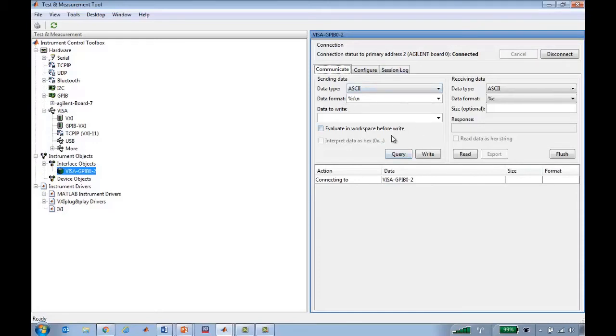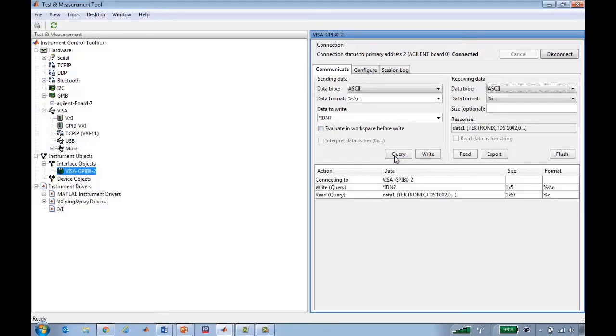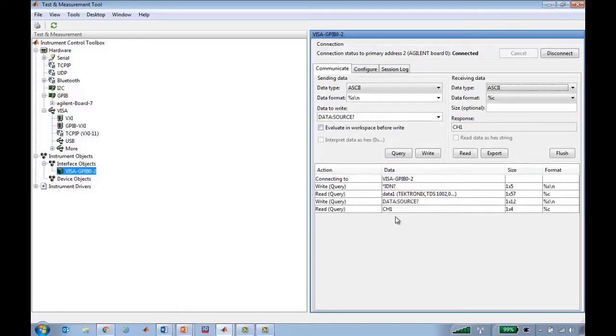In the Communicate tab, I have an interface where I can send raw data or send ASCII commands back and forth. A very common command that you'd want to send is star IDN. This asks the instrument to identify itself, and this is a common SCPI command that almost all instruments have. If you're familiar with the SCPI command set for your instrument, you can run some of those other commands, available in the programming manual. So I could say data source to see which channel is being read on the instrument, and you see it's channel one.